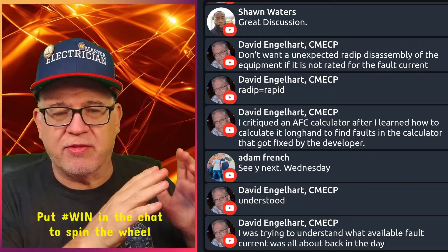What I tried to do is not dig into the weeds. If I looked at what their available fault current was, and their equipment upstream was equal to or greater than their available fault current, then I know that equipment downstream, which is typical standard industry, I didn't even have to worry about it. Whatever they gave me, as long as it was stamped and it says it was equal, I'm fine with that. I'm not going to get into the weeds, because it's physically impossible in my mind to have a 20,000 available fault current at a service, have service equipment rated for, let's say, 35,000 in a commercial, and then go downstream.